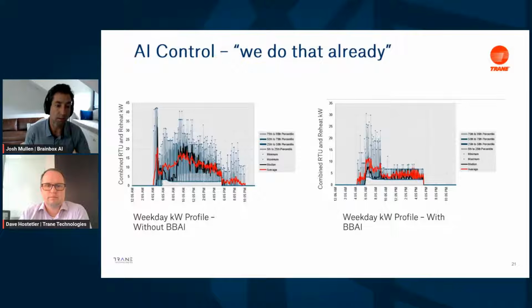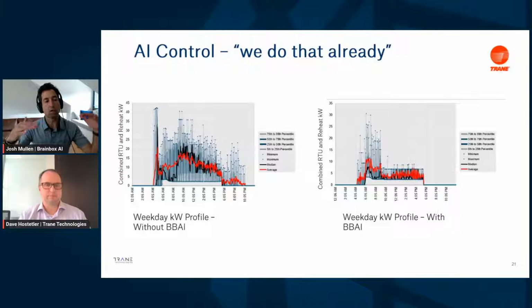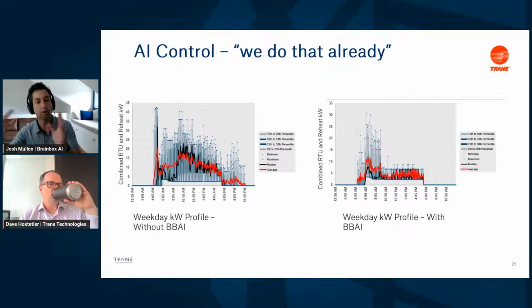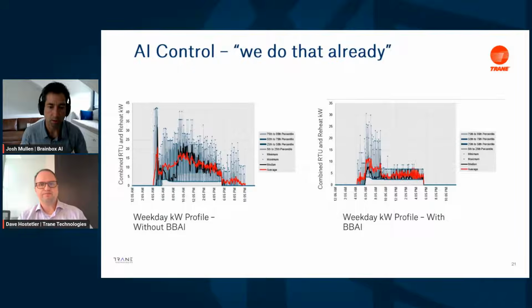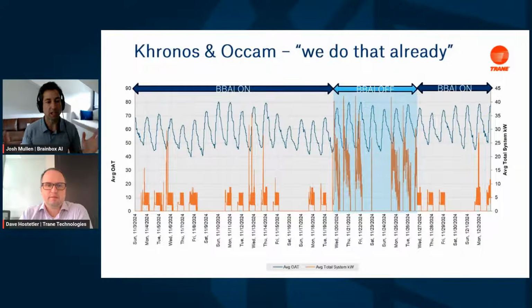And get more granular savings. So here's an example of a building that had optimum start, supply air temperature, and static pressure reset. It was a self-contained multi-zone rooftop unit with electric reheat, and you can see it's slamming on in the morning, about a 45 kW morning warm-up peak. With us, it's no longer slamming in the morning, and the total peak is lower, around 30. So we're reducing not only the morning warm-up peak but the overall energy consumption throughout the day as well.